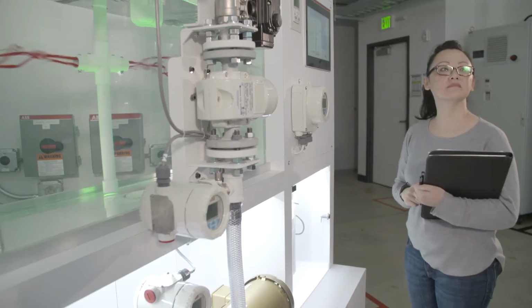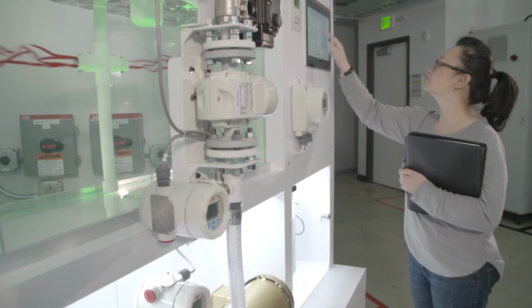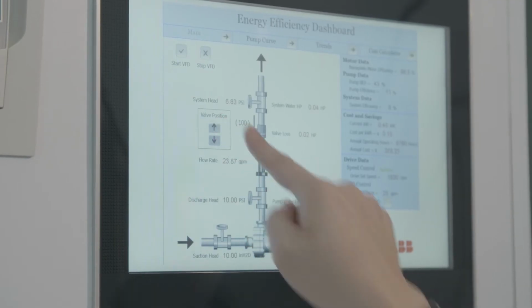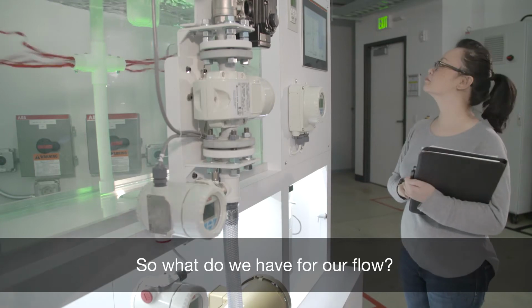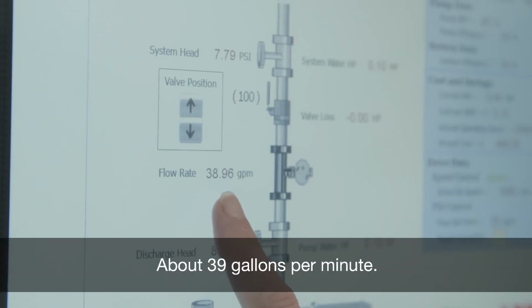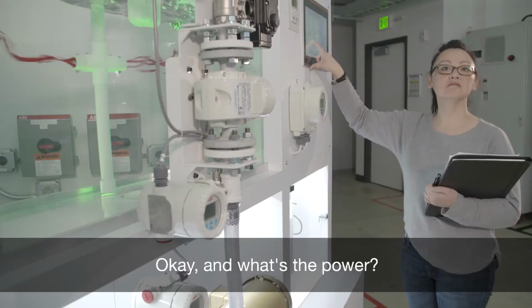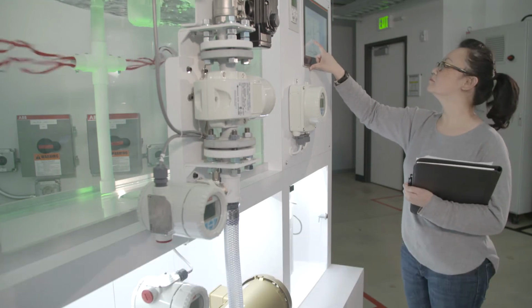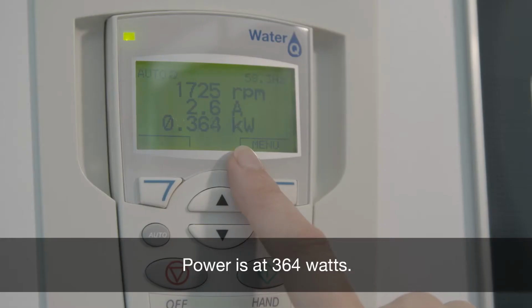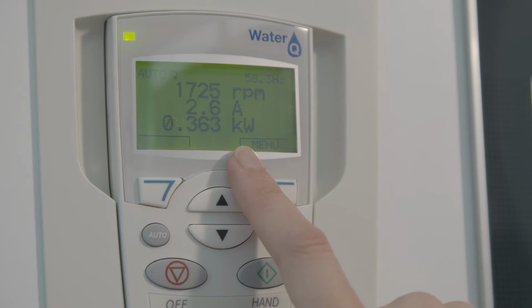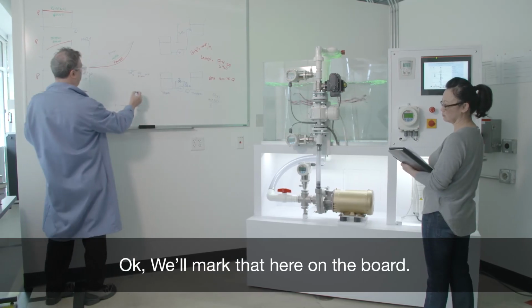Great. Now let's open the valve all the way. So what do we have for our flow? About 39 gallons per minute. Okay, and what's the power? Power is at 364 watts. Okay, we'll mark that here on the board.